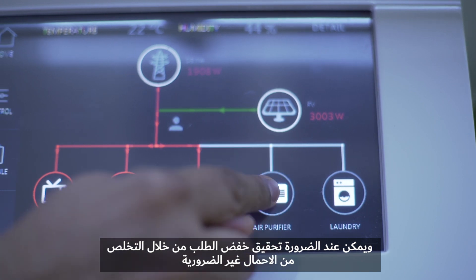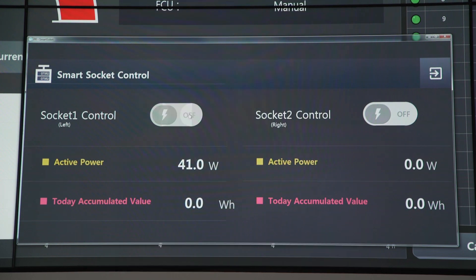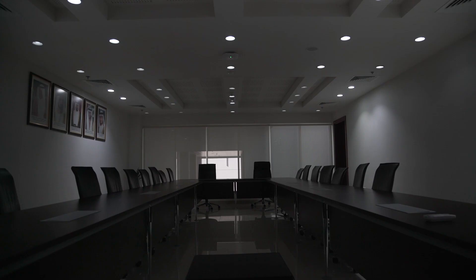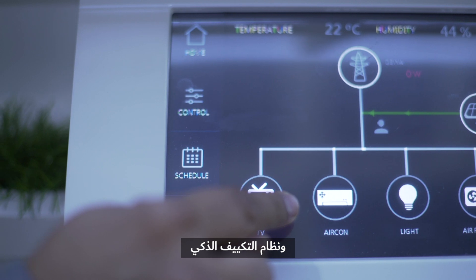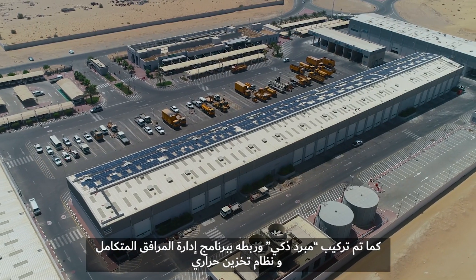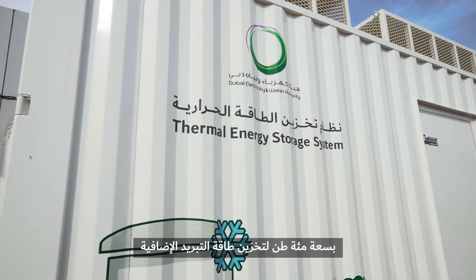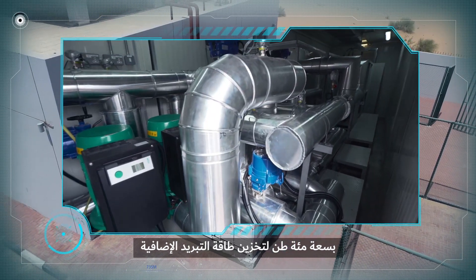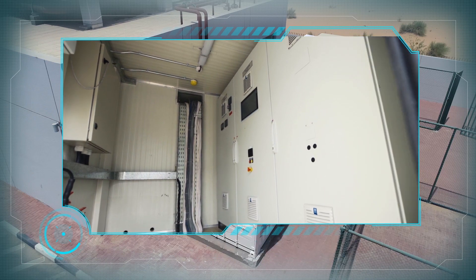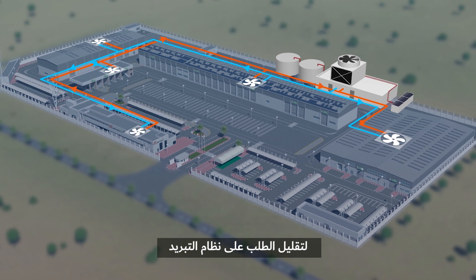When required, demand reduction can be achieved by shedding non-critical load through the control of the smart lighting, the smart power outlets, and the smart air conditioning system. The DEWA Smart Grid Station is integrated with the smart chillers through a building management system. It also utilizes a 100-ton thermal energy storage system which stores surplus cooling energy, which can be utilized when needed, thereby reducing the demand on the chillers.